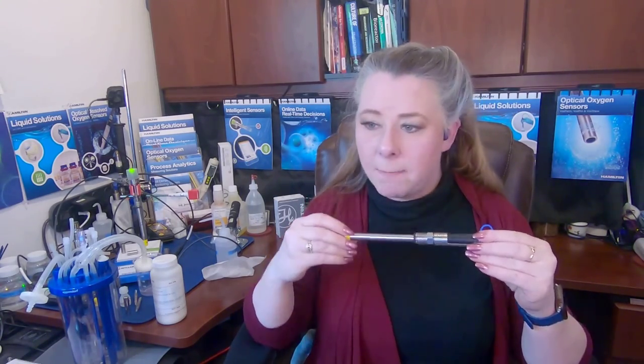Conversely, this optical sensor might be $2,000 up front. These are not real prices, but they're ballpark, okay? You might need to replace that cap every 6 months, which is pretty typical. So 2 caps a year. Your first year cost of this is going to be right around $2,400 versus $4,000. Your second year cost, assuming you don't have to replace the sensor, for 2 years, you're looking at about, call it, $2,800 for this, and about $7,000 for this. And that does not count labor or downtime due to polarization.